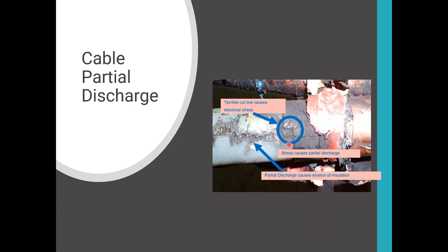So that's when we said workmanship, and workmanship issues play back a lot into training and explanations in instruction manuals. What does it mean to do a cutback? What does it mean to clean stuff? These are examples of where that wasn't understood or wasn't followed and resulted in a bad failure. And as soon as that cable is energized, you're going to start to see this PD develop. So this is one that would be an example of potentially an early life failure that would be detected on initial energization.